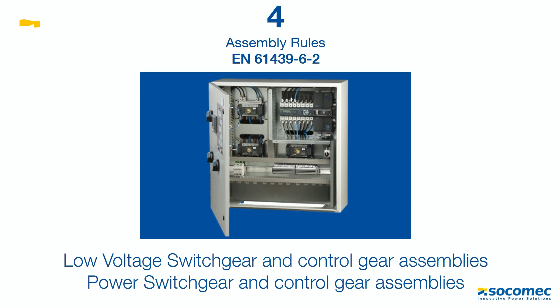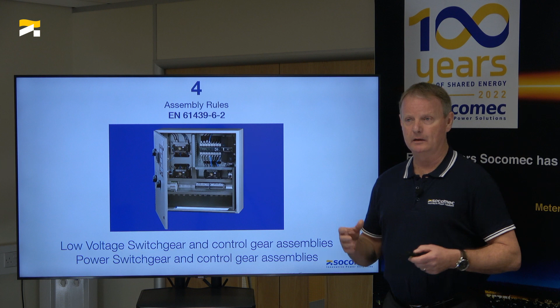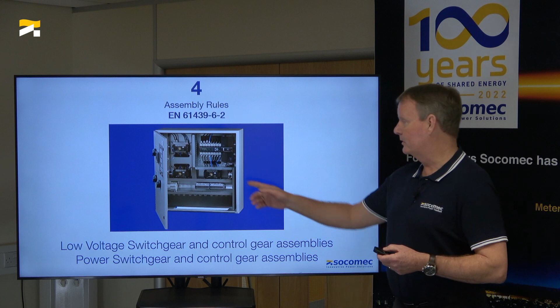Each one of those products, like the ATS, the changeover switches, the isolators, is tested in isolation to the product standard. So it's a big area we see, with a lot of questions around whether you can give a test report, or assume a test is done, because you're using all products approved to the standard.